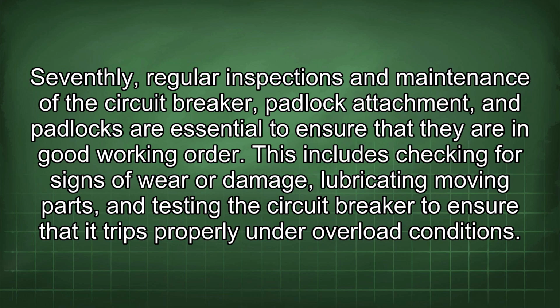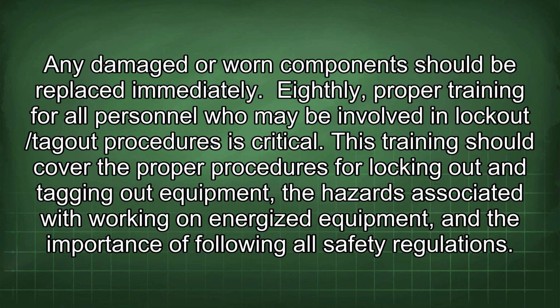Seventhly, regular inspections and maintenance of the circuit breaker, padlock attachment, and padlocks are essential to ensure that they are in good working order. This includes checking for signs of wear or damage, lubricating moving parts, and testing the circuit breaker to ensure that it trips properly under overload conditions. Any damaged or worn components should be replaced immediately.